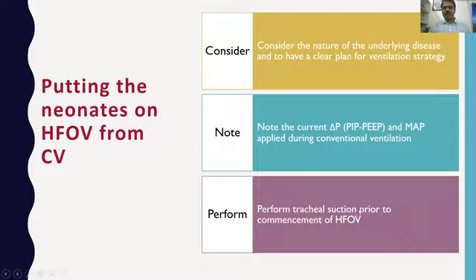And you have to perform endotracheal suction, as I discussed in the previous slide. So now you have set your machine, and what are the circuit factors to be considered while using high frequency ventilation? This is another important aspect. Whenever you are thinking of starting high frequency ventilation, you may need to change your ventilator circuit also. These are particular properties of the ventilator circuit which you should know. The ventilatory tubings which you are going to use should be very stiff. There should not be any kinks, and they should be as short and as straight as possible.